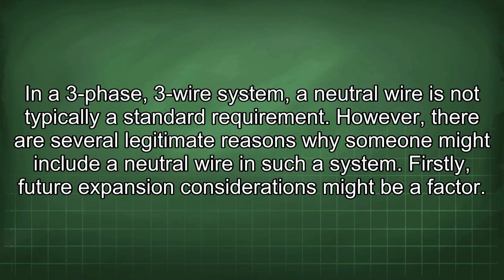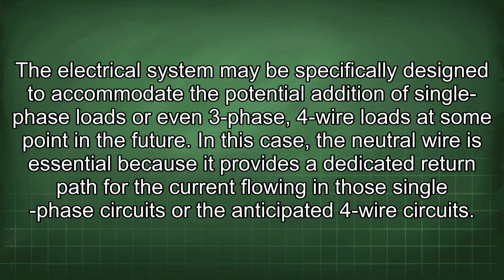In a three-phase, three-wire system, a neutral wire is not typically a standard requirement. However, there are several legitimate reasons why someone might include a neutral wire in such a system. Firstly, future expansion considerations might be a factor. The electrical system may be specifically designed to accommodate the potential addition of single-phase loads or even three-phase, four-wire loads at some point in the future.